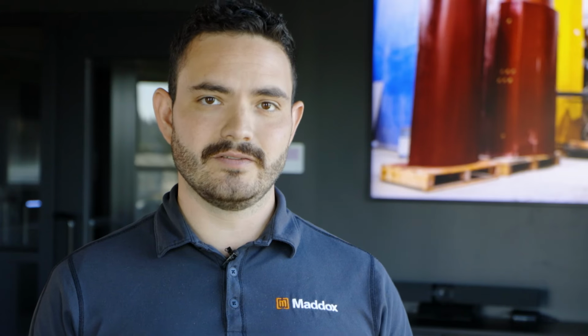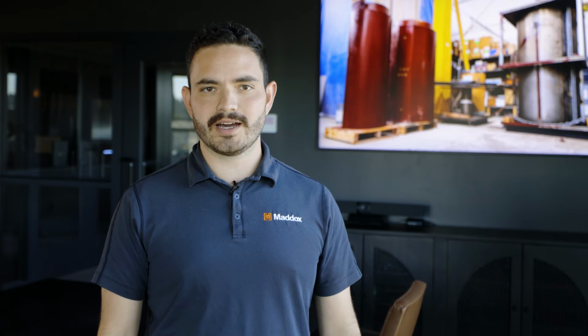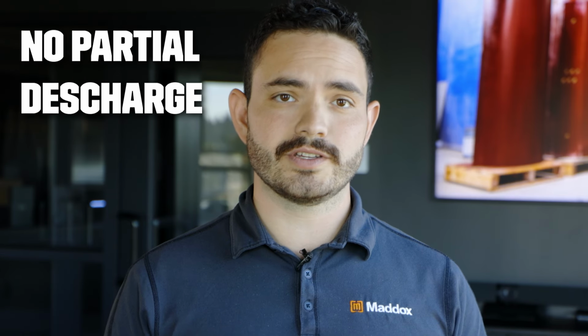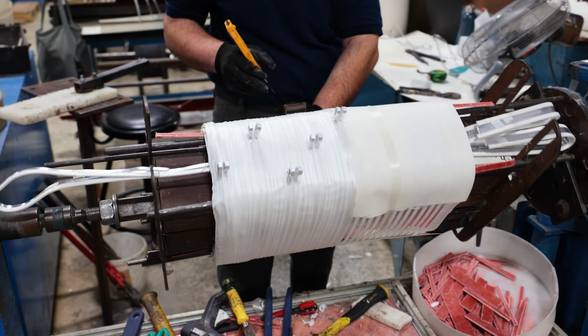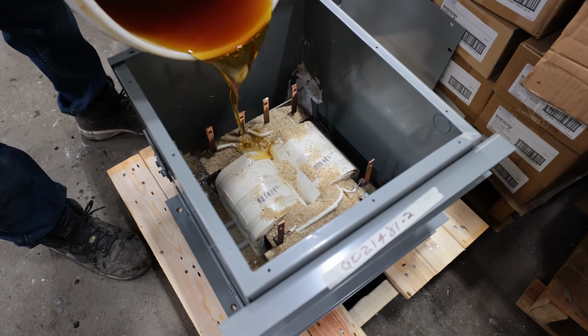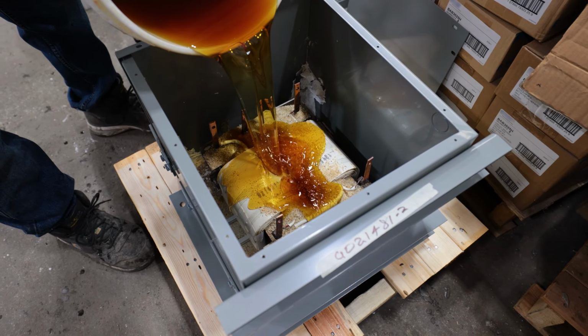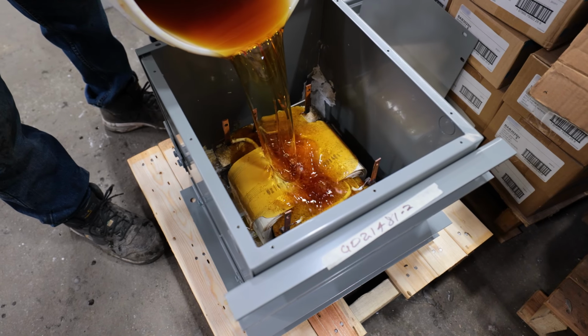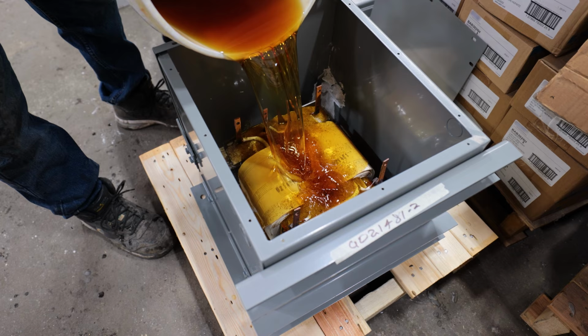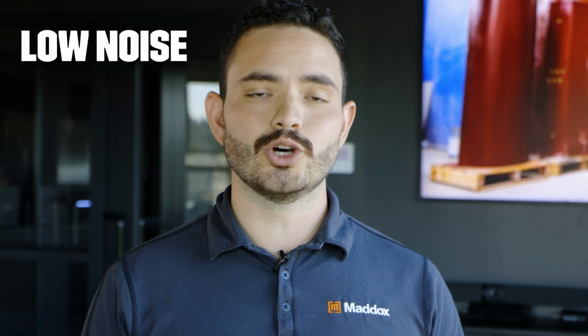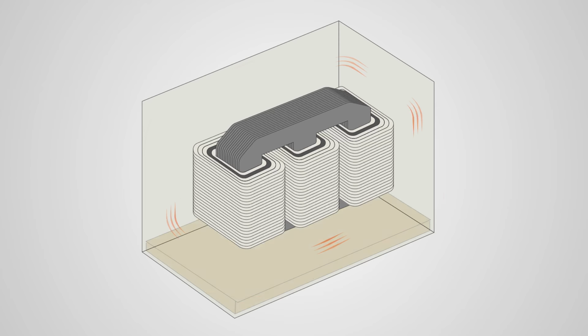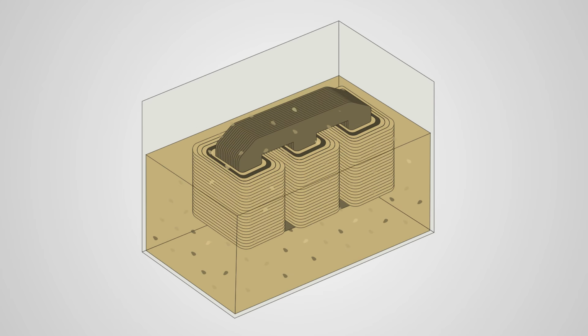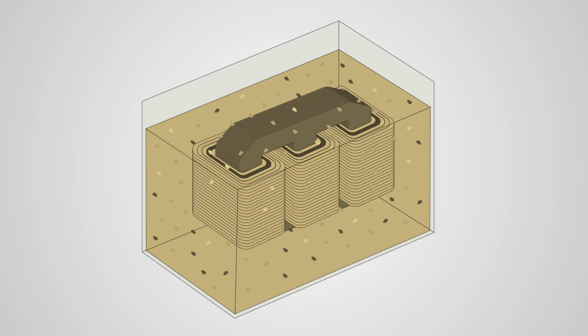Those are the basics of two types of cast resin transformers. So why would you choose one of these over a regular VPI dry type? First, no partial discharge. Partial discharge is a localized dielectric breakdown that occurs in air gaps inside a transformer's insulation. However, the epoxy in a cast resin transformer covers the windings completely, eliminating any possibility of air pockets and partial discharge. Second, low noise. The resin locks the transformer windings in place, which minimizes vibration and any subsequent noise.